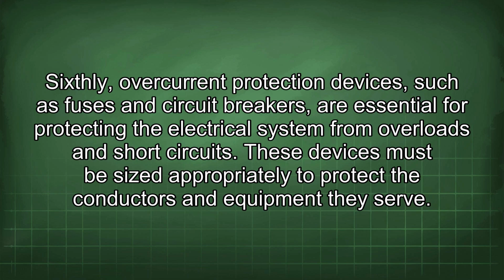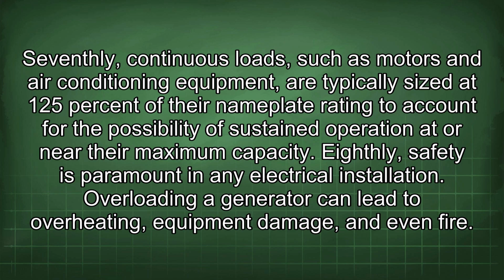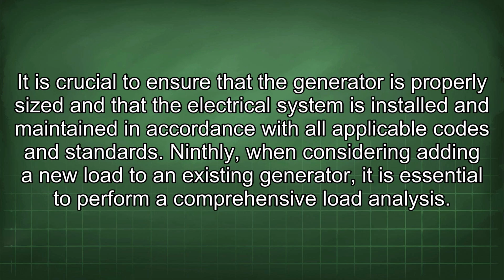Sixthly, overcurrent protection devices, such as fuses and circuit breakers, are essential for protecting the electrical system from overloads and short circuits. These devices must be sized appropriately to protect the conductors and equipment they serve. Seventhly, continuous loads, such as motors and air conditioning equipment, are typically sized at 125% of their nameplate rating to account for the possibility of sustained operation at or near their maximum capacity. Eighthly, safety is paramount in any electrical installation. Overloading a generator can lead to overheating, equipment damage, and even fire. It is crucial to ensure that the generator is properly sized and that the electrical system is installed and maintained in accordance with all applicable codes and standards.